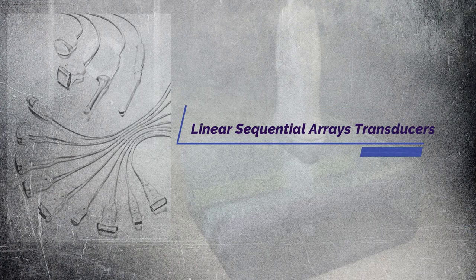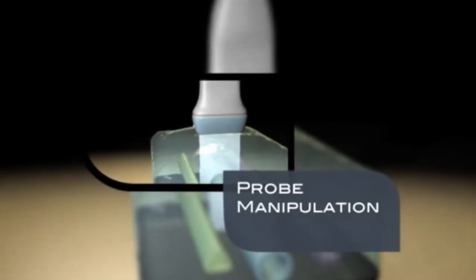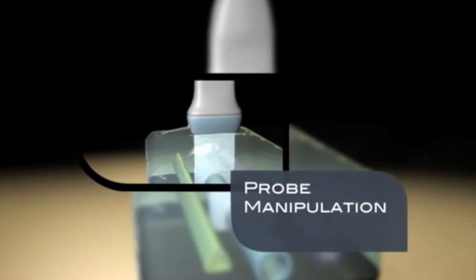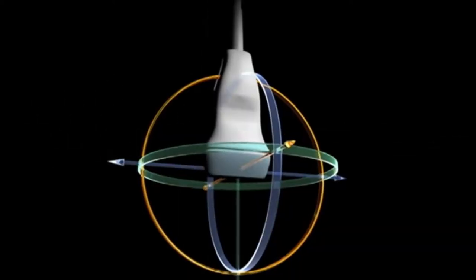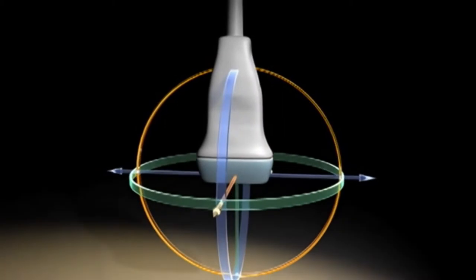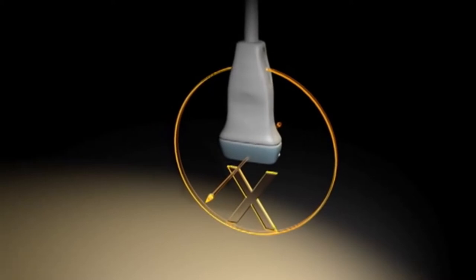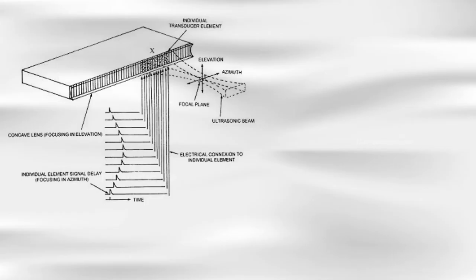Let's know about linear sequential array transducers. The scanning lines are directed perpendicular to the face of the transducer. The beam is focused but not steered. Linear array transducers are available with 512 elements in currently available ultrasound scanners. Generally, up to 128 elements are selected at a time for operation. As is obvious from the diagram, the field of view with a linear array arrangement is limited to the rectangular region directly in front of the transducer.